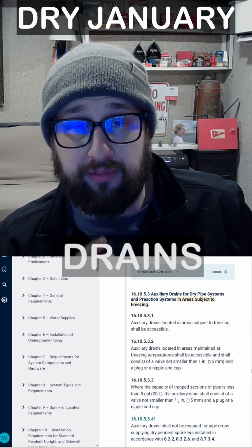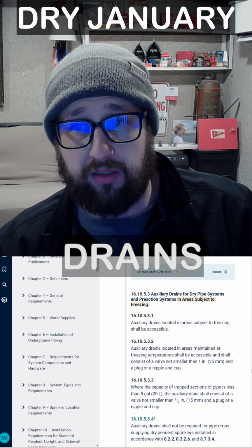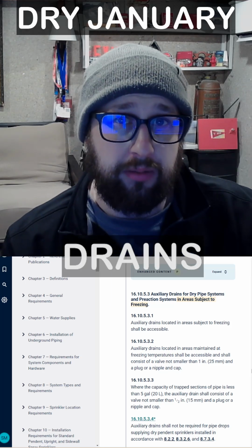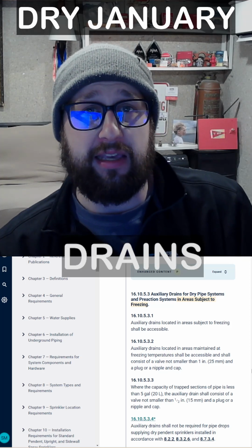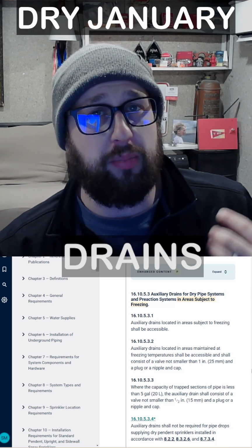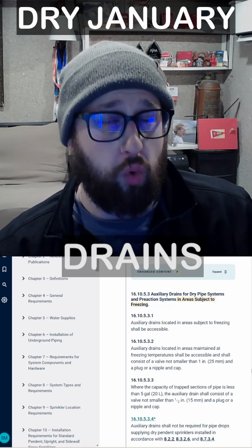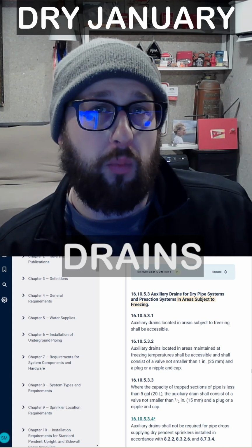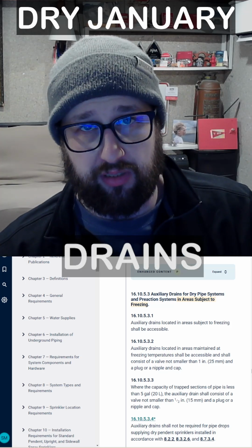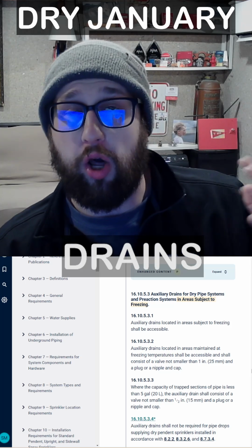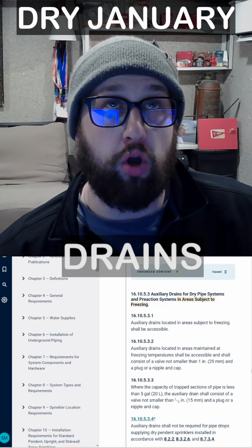It's dry January. Let's talk about auxiliary drains. Now, if you have a dry pipe sprinkler system, the reason most likely is that you can't maintain the temperature above 40 degrees Fahrenheit, which means water would freeze. So you need a way to get water out of that system if it were to be introduced into the system. So water can be introduced in multiple different ways.